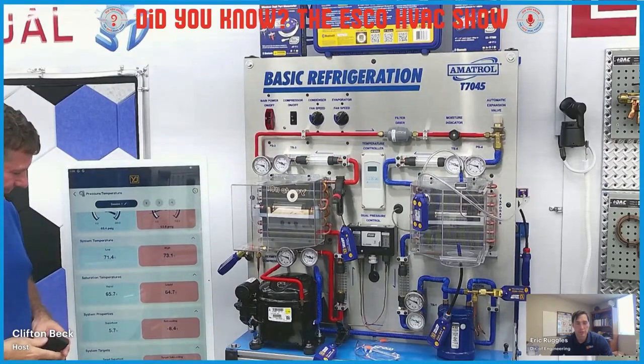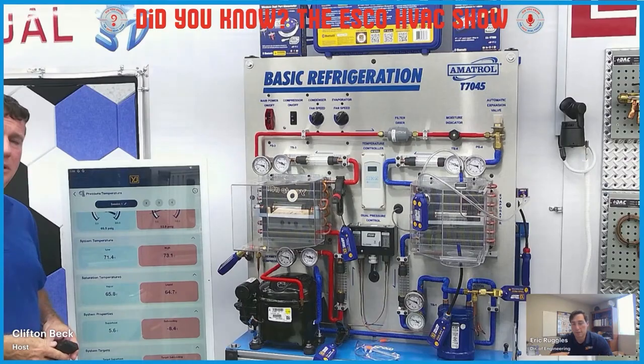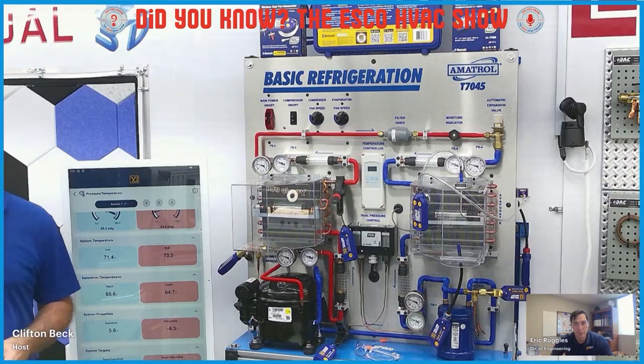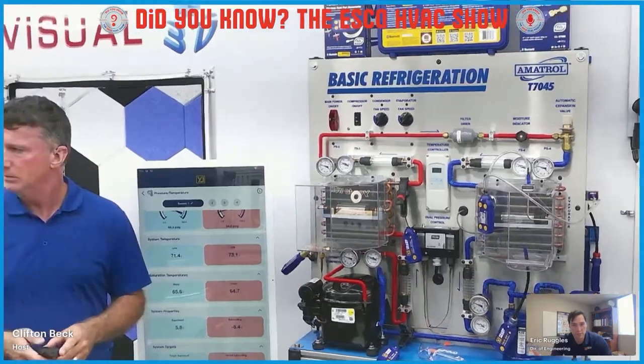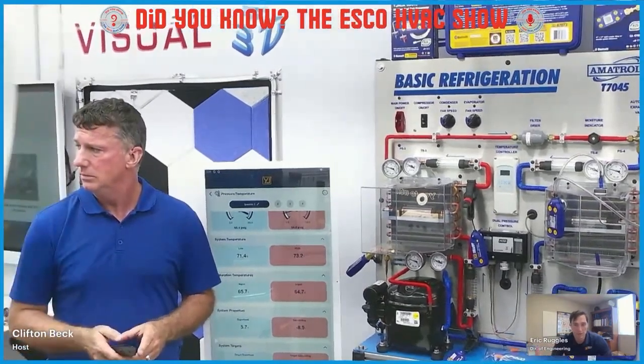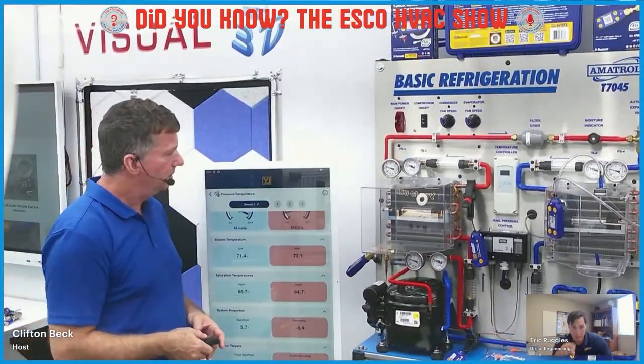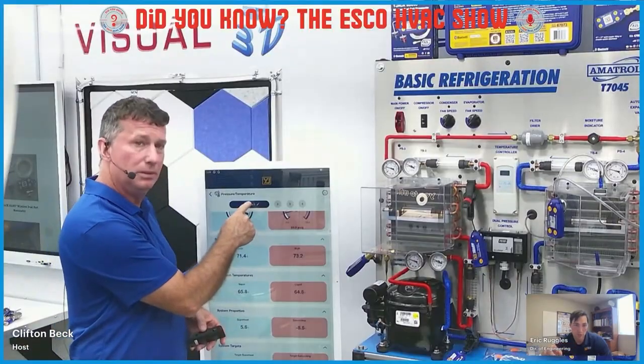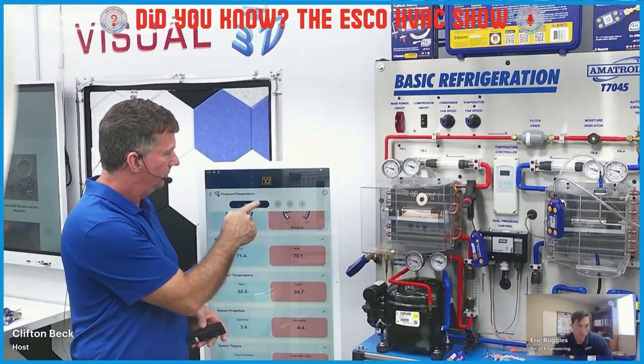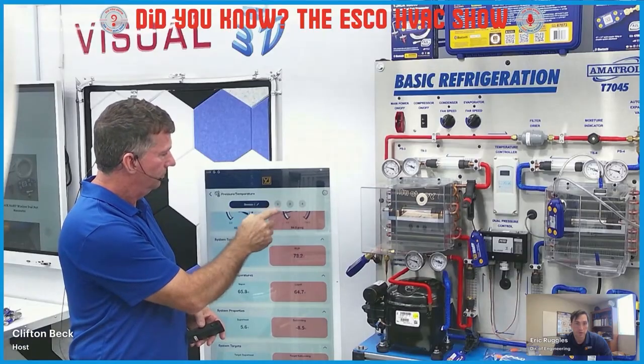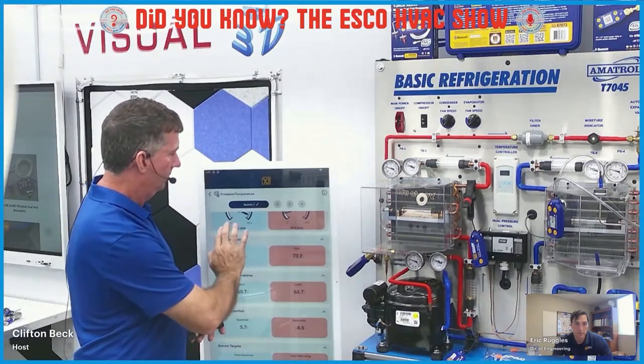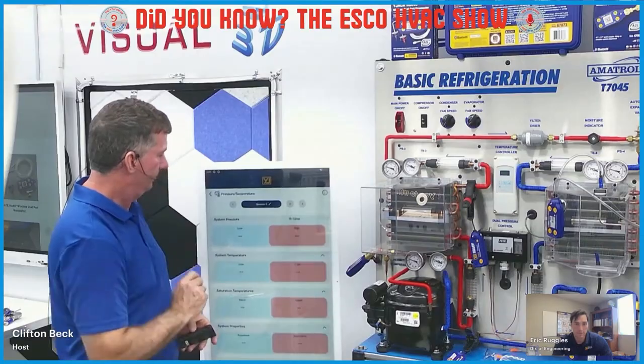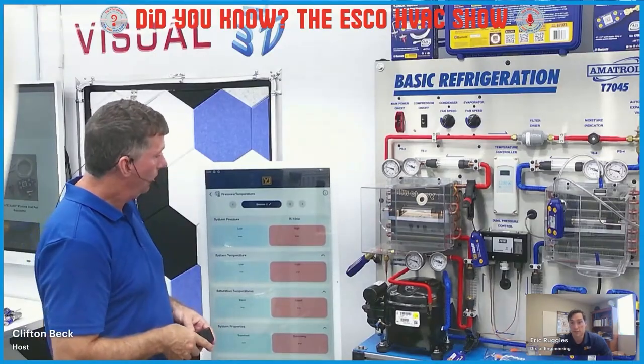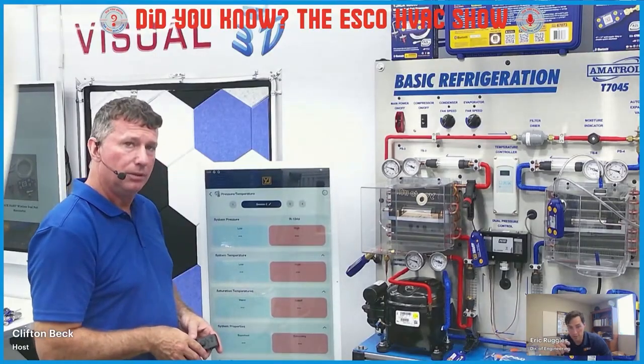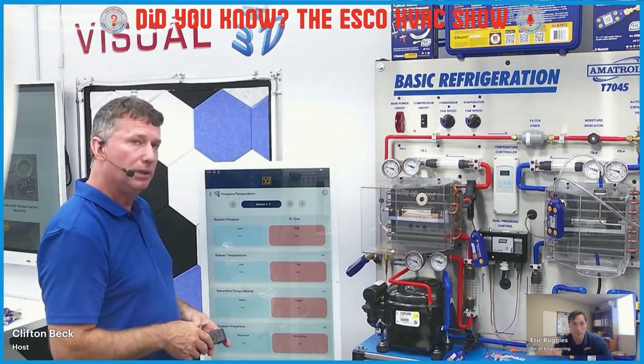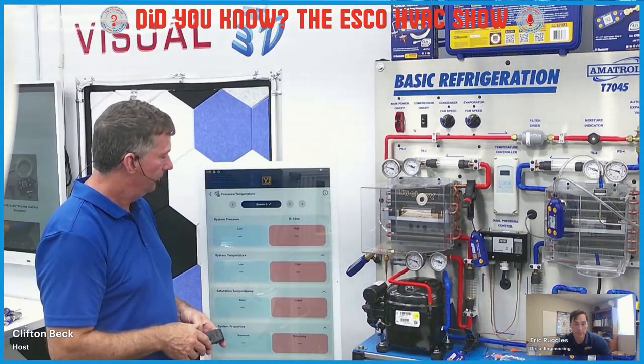Yep. Okay. So the other advantage on here that maybe isn't typical for a lot of techs, but those that are commissioning a lot of units may have a number of sets of sensors that are setting up multiple sensors at the same time. So at the top of that screen, it says session 1, in the large bubble. If you swipe to the left, you can jump to another session. Oh, the whole screen, just in the middle of the screen. Other way. Oh, that'd be right. Yeah. So you can connect another set of sensors, and then you can swipe back and you can relabel those Unit 1 or RTU1, RTU2, or whatever you're doing. Up to 4 sessions at the same time.